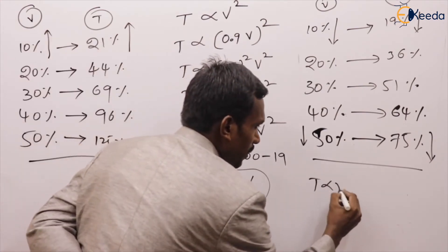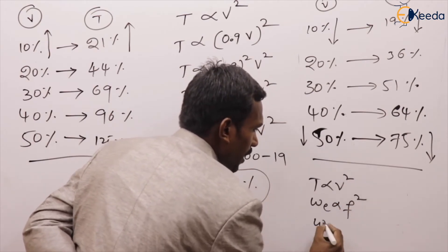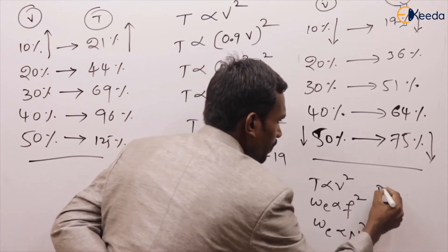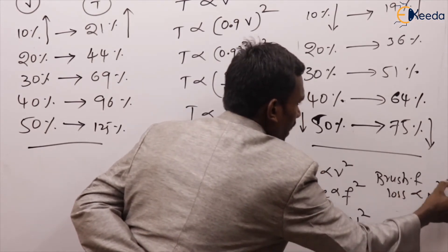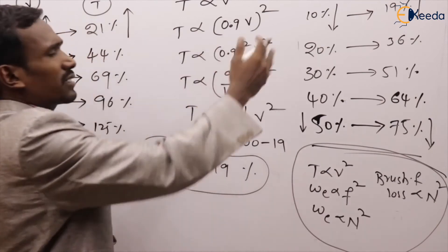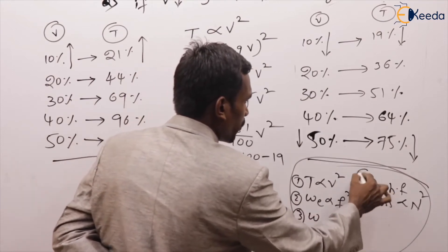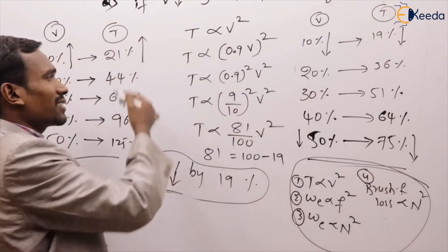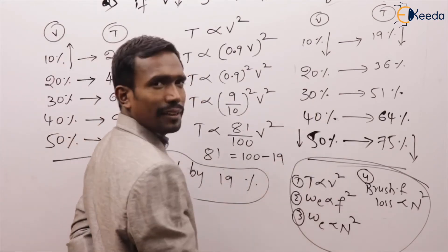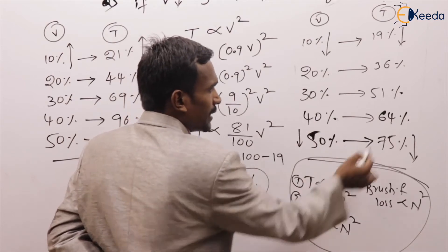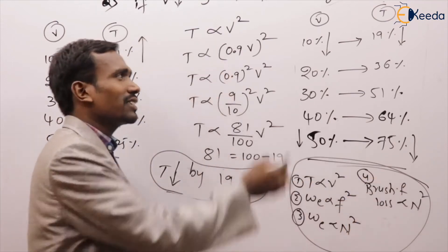For all square-law quantities — torque directly proportional to V squared, eddy current loss directly proportional to F squared or N squared, brush frictional losses directly proportional to N squared — the answers are the same. For example, if speed reduced by 30%, eddy current loss is reduced by 51%.